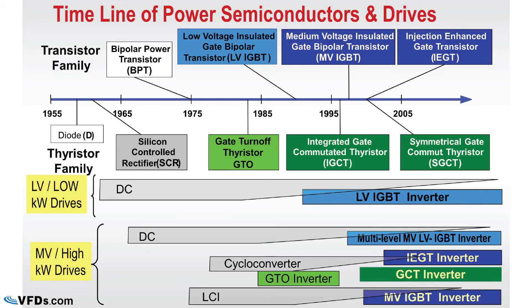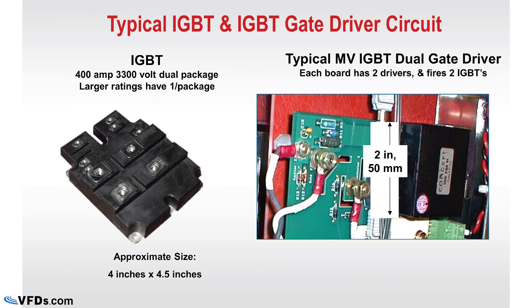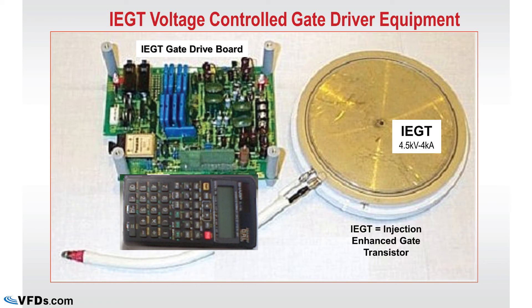Here's a timeline of drive development. In my opinion, the low voltage drive first became reliable in about 1988 with the introduction of the low voltage IGBT. Medium voltage drives have taken longer and underwent considerable development during the 1990s and in the first decade of the 21st century. The most common device used in a medium voltage drive is called a medium voltage IGBT — the standard building block of today's modern drives. Another device is used basically only in drives of 10,000 horsepower or higher — an amazing device barely bigger than a calculator that can withstand 4,500 volts and 4,000 amps.